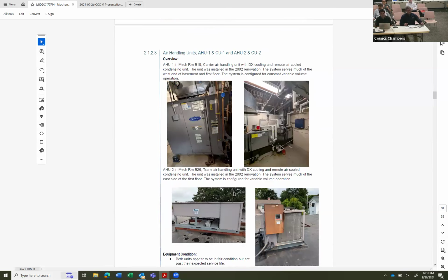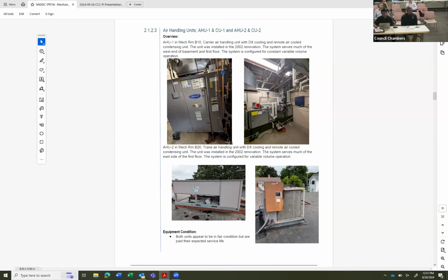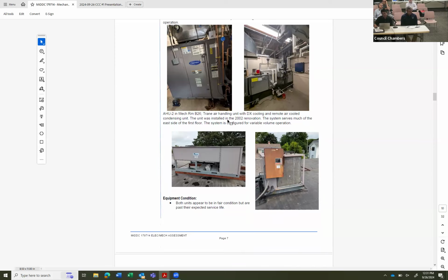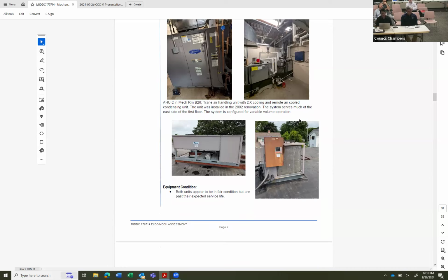And looking at the air handlers, air handler one in the basement, room B10, is a unit that was installed in the 2002 renovation. It serves much of the west end of the basement and the first floor. It's configured as a constant and variable volume. Or sorry, this one is a variable volume operating unit. And there's a second air handler in the basement that was also installed in the 2002 renovation. So the system appears to be working well, but it's a little bit past the expected service life.